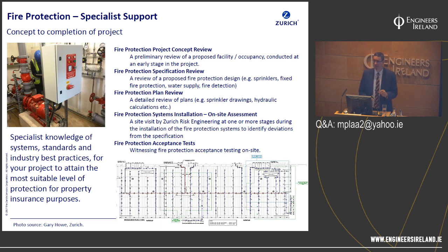Too often we're finding in the field that fire officers, building control officers and fire engineers are simply relying on a piece of paper from an installer and going, thank you very much, I've got a commissioning certificate. Well, we have a saying in Zurich, the certificates don't put out fires. And too often the industry is relying on pieces of paper as a means of validating designs and installations. It's our opinion that that simply isn't good enough, and it lulls you into a false sense of security. And that's why we don't accept pieces of paper as means of verification of system designs.